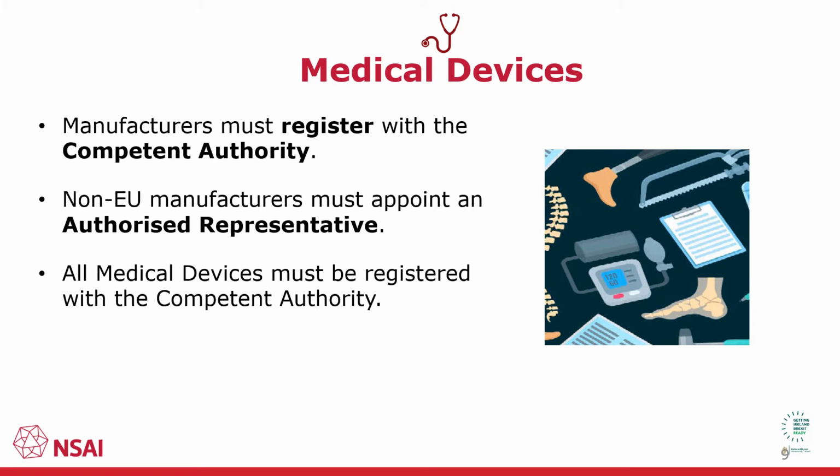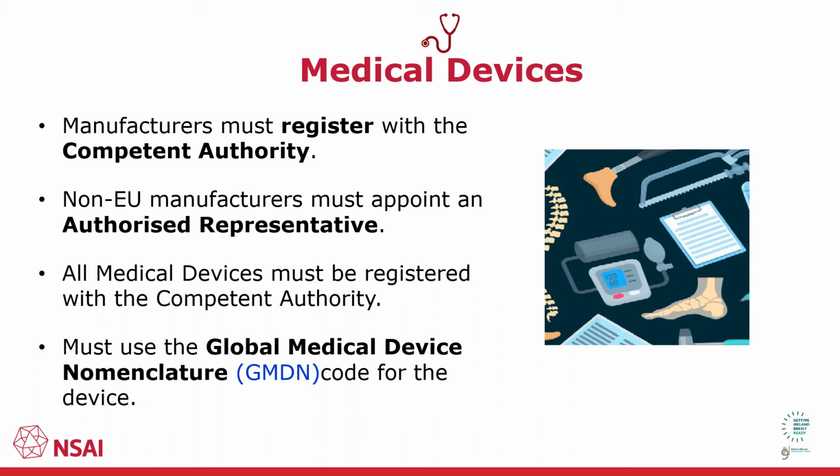They must register all medical devices with the competent authority in the designated language of the member state in which they are being registered. The Global Medical Device Nomenclature is an international standardized nomenclature to accurately describe and catalogue medical devices and other healthcare products. The appropriate GMDN code must be used for all devices being registered. GMDN will be replaced under the MDR by the EMDN, or European Medical Device Nomenclature System.